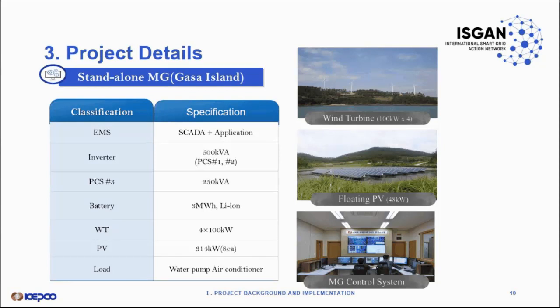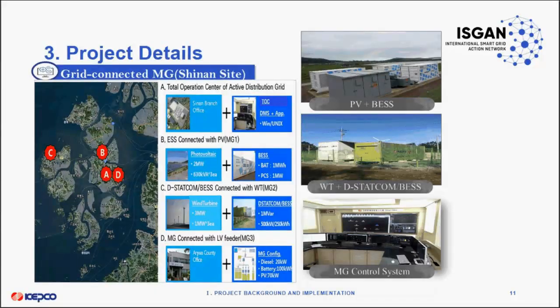Let me talk about the MG system, EMS, which stands for Energy Management System. A key component of standalone MG is specifically used to forecast load and renewable energy output and manage battery state of charge. The inverter is designed to keep frequency and voltage in a relative range, and the PCS is aimed at helping control active and reactive power in case of shortage of rating. Lastly, water pump and air conditioner in the battery room are used as pseudo load in the event that surplus energy is produced.